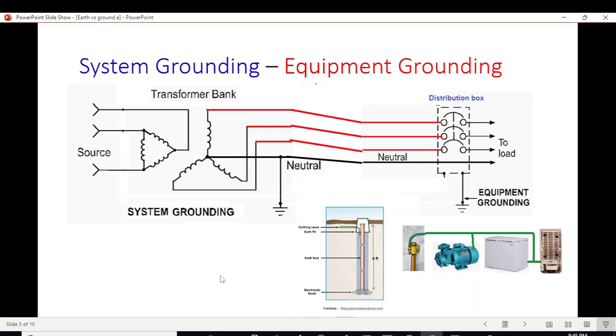And now actually, if you see, the phase supply and the neutral from the transformer is connected to the phases or phase connection in the house, and this terminal is now called the neutral. So neutral in one phase, neutral in other phase, neutral in third phase. This is how this system works, or the supply works. But if you see, this is connected to the body of all devices. So this is also ground, this is also ground, but they are not the same. They are at two different places, and through underneath, through the ground, it is connected, but there may be some difference in the potential. So we'll see that.